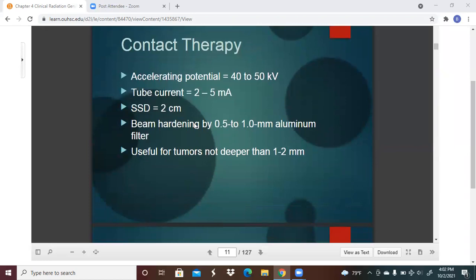So now let's look at contact therapy. The accelerating potential is 40 to 50 kilovolts. Tube current is 2 to 5 milliamps. SSD is about 2 cm. Beam hardening by a half to a full millimeter aluminum filter. And it's useful for tumors not deeper than 1 to 2 millimeters.